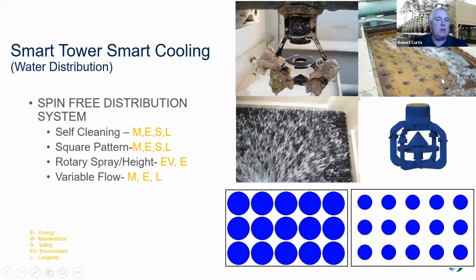The first thing you see on this slide are pictures of a traditional cooling tower nozzle system on the top left, and a traditional basin on the right. Those nozzles have very small orifices that tend to scale up, causing fouling of the distribution system.